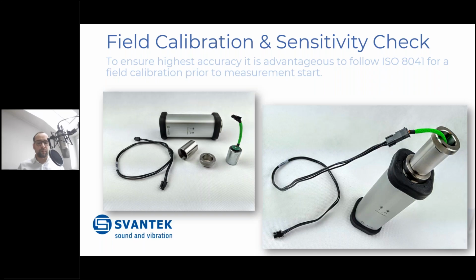Let's say that we deploy a device that is supposed to measure the vibration at an inspection stand where you have these very high level microscopes. The technicians or people manning these will be able to tell if it's blurry or not. But if your device deployed out there shows levels well below VCC while they are complaining on these levels, then that means that perhaps your calibration factor on your geophones is not up to date.